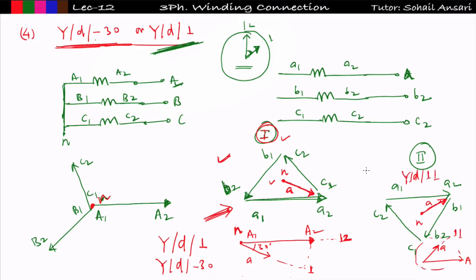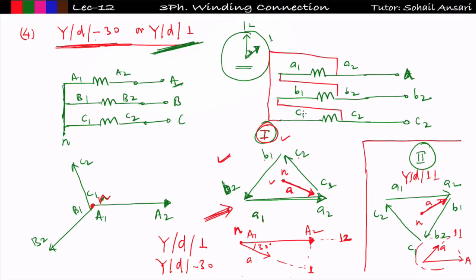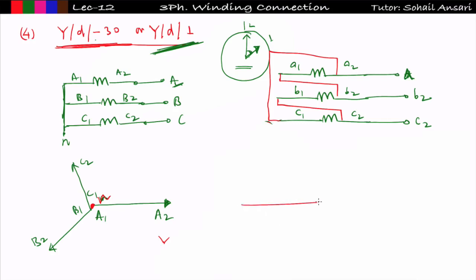I need to make YD1, not YD11, so Case 2 is not valid here. The valid connection is: A2 connected with C1, C2 connected with B1, and B2 connected with A1 — equivalently, A1 is connected with B2, B1 with C2, and C1 with A2. This is the connection diagram of YD1 (YD-30). The final phasor diagram shows A2-A1, with A1 connected to B2, then B2-B1, and C2-C1, with the line-to-neutral voltage 'a' lagging 30 degrees.